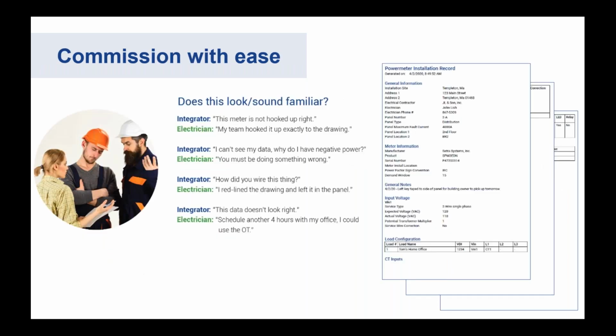The other thing we wanted to do is address the lot of handoffs within a metering job. Sometimes there's a separate electrical contractor, there's an integrator, sometimes there's a building owner in there. What we wanted to do is streamline the installation as well as aid in commissioning. So we made an installation record that you can generate from the software. With that installation report, you can get all the information of how that meter was configured through the software, as well as see a snapshot of a measurement value for the CTs and the voltage inputs. It also gives you a spot to type in some multimeter values. So should you want to measure the amperage or voltage that's coming in, you can do so, type in that comparative value, and see how those lined up with your meter for a commissioning phase to make sure everything is hooked up right.